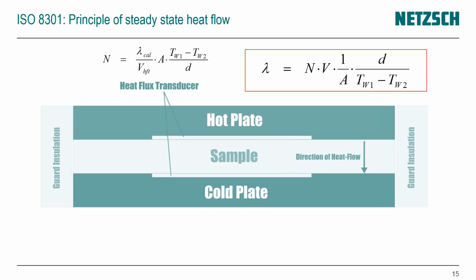Due to the fact that those heat flux transducers, over a certain temperature range and a certain range of different heat flows, are not linear at all, a heat flow meter is a method which needs to be calibrated. It is calibrated by inserting a known sample, a so-called reference sample. With this reference sample with a known thermal conductivity, you can calculate, or the instrument itself calculates, a correction factor, which brings your measurement to a level which is traceable to an internationally recognized reference material.